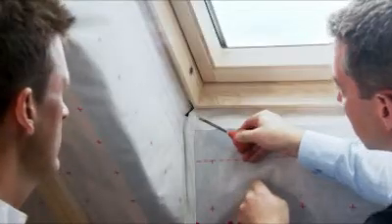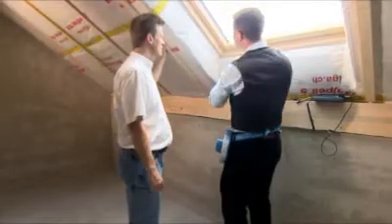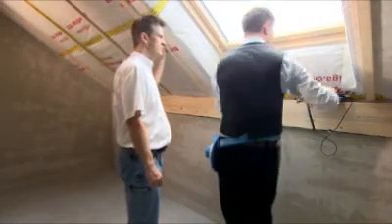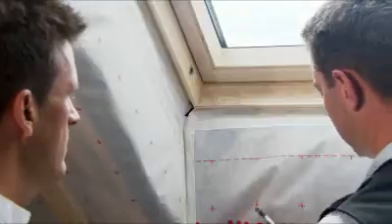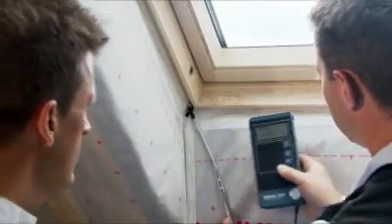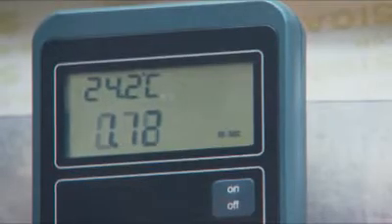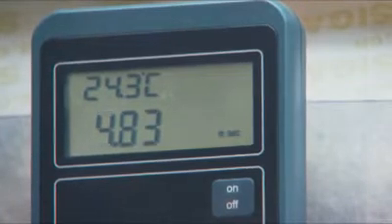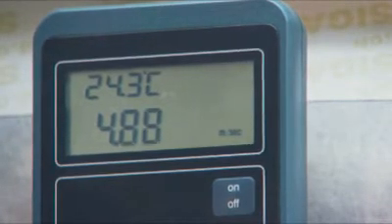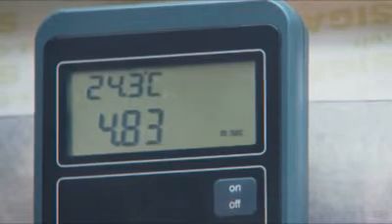Using a smoke tube, leaks can be detected and air flows can be made visible. A thermal anemometer is used to measure the speed of the incoming air. We perceive inflowing air with a speed of more than 0.2 metres per second as unpleasant. It feels drafty.